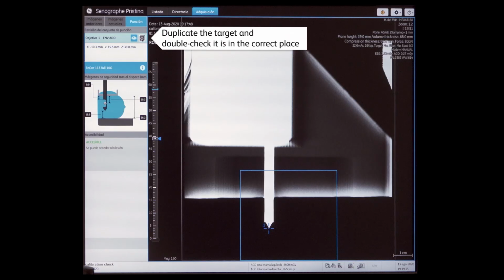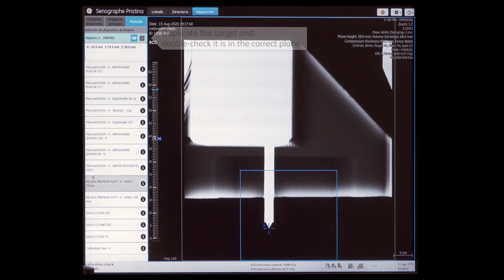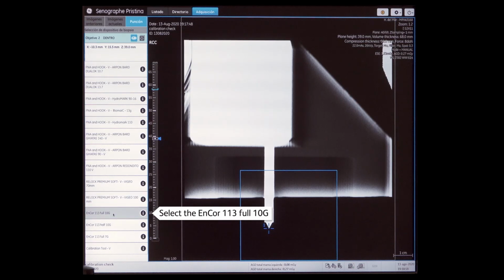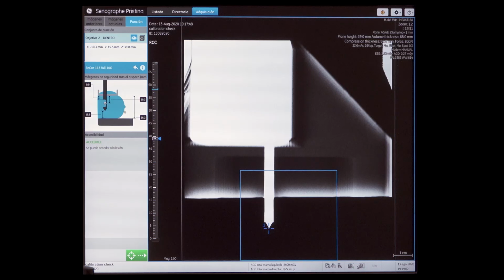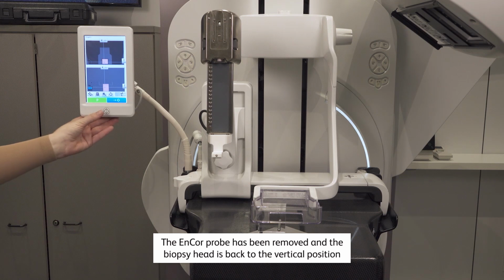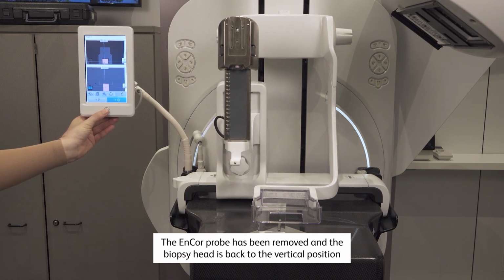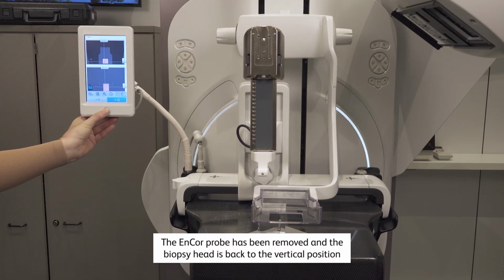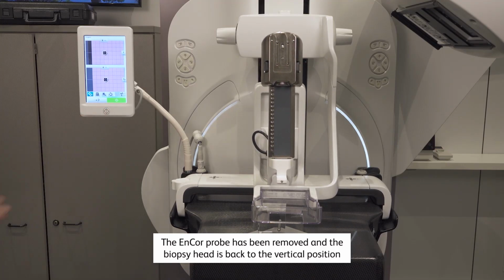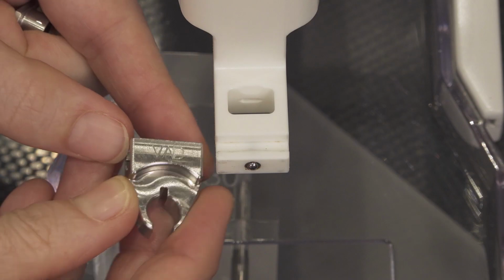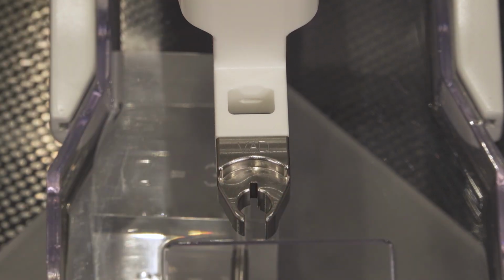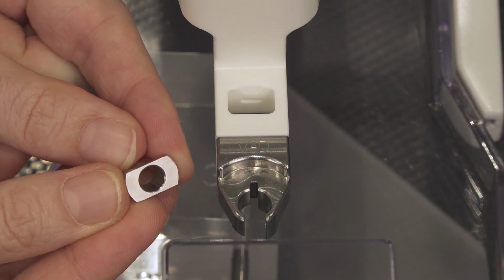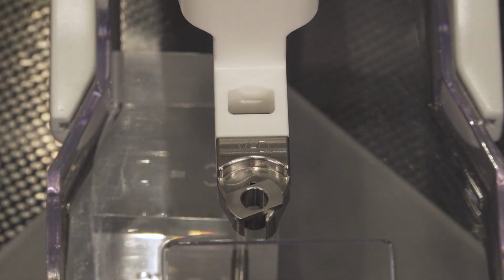Calibration accuracy check for EnCor 113 10G vertical approach. The target button is highlighted in blue. Press the screen hardware button to drive the biopsy head to the target coordinates. The target button changes to green. Insert the VAD vertical needle guide support. Insert the 10G EnCor needle guides, both metallic and plastic.